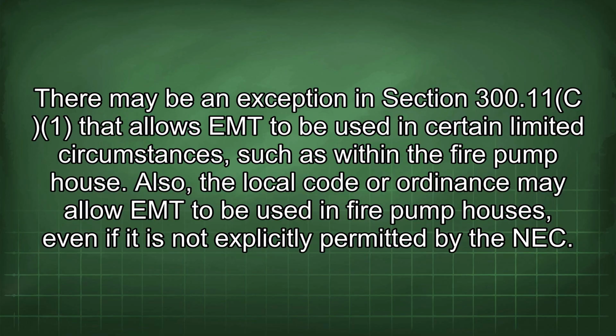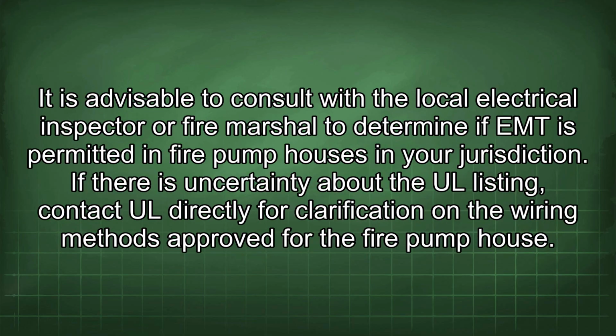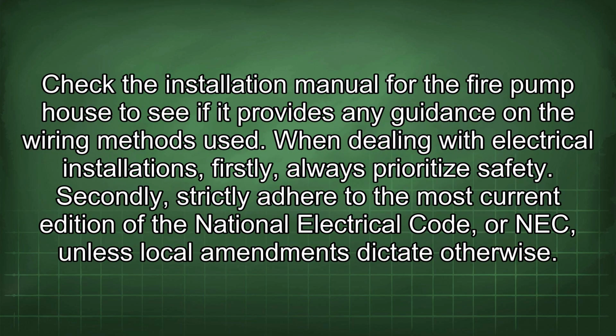Also, the local code or ordinance may allow EMT to be used in fire pump houses, even if it is not explicitly permitted by the NEC. It is advisable to consult with the local electrical inspector or fire marshal to determine if EMT is permitted in fire pump houses in your jurisdiction. If there is uncertainty about the UL listing, contact UL directly for clarification on the wiring methods approved for the fire pump house. Check the installation manual for the fire pump house to see if it provides any guidance on the wiring methods used.